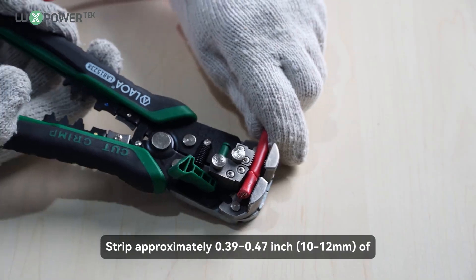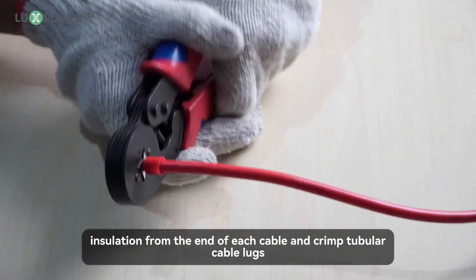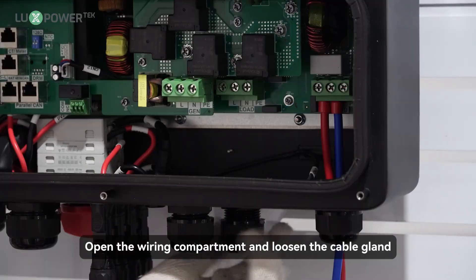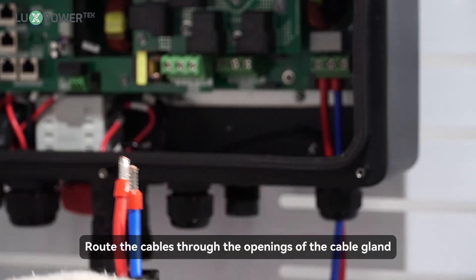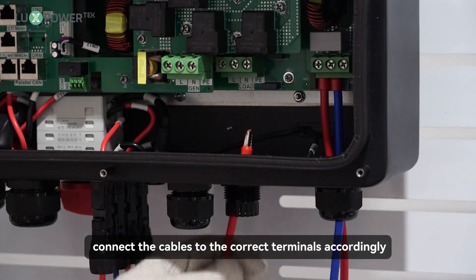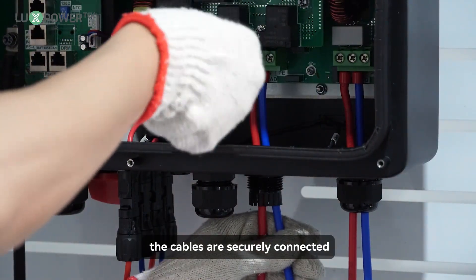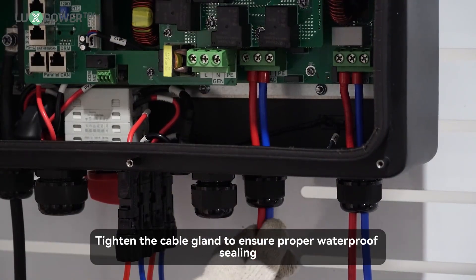Step 1: Strip approximately 0.39 to 0.47 inch of insulation from the end of each cable and crimp tubular cable lugs. Step 2: Open the wiring compartment and loosen the cable gland. Route the cables through the openings of the cable gland. Step 3: Refer to the labels inside the wiring compartment and connect the cables to the correct terminals accordingly. Step 4: Tighten the screws above the terminals to ensure the cables are securely connected. Step 5: Tighten the cable gland to ensure proper waterproof sealing.